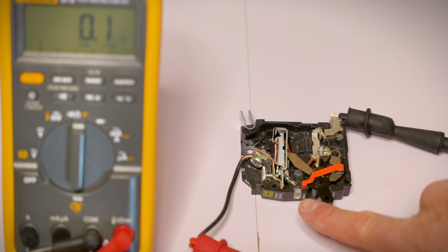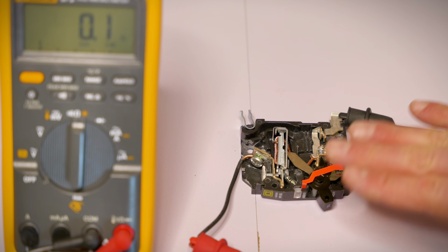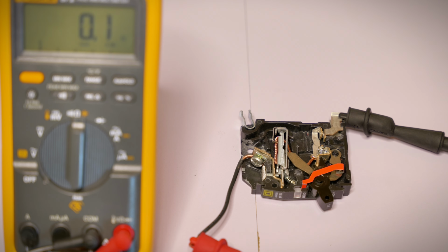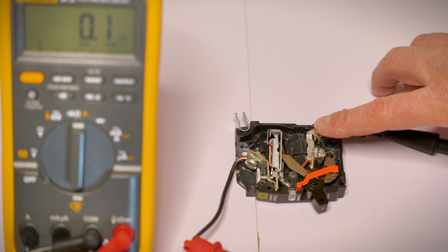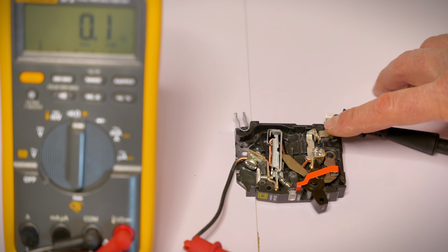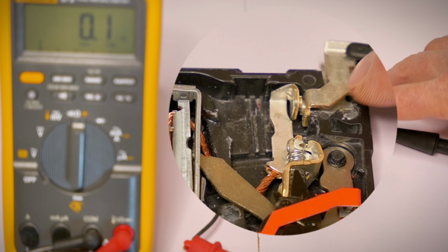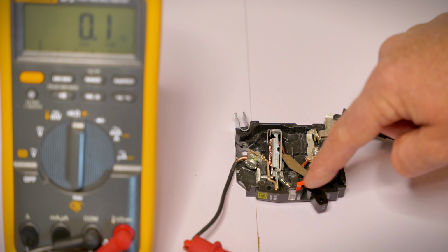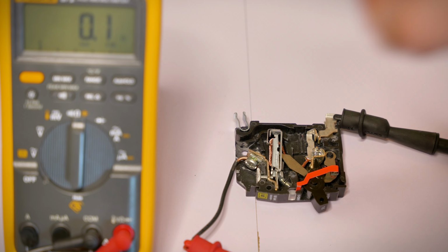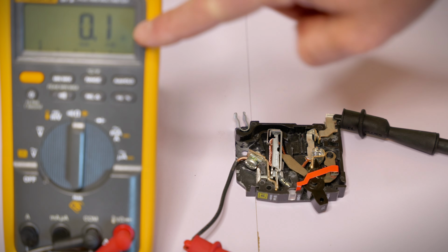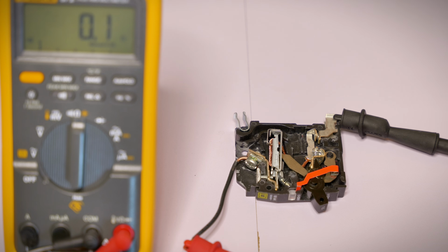You no longer have the orange flag in the window, so everything seems to be operating normal with the circuit breaker. You can also tell that the moving contact arm there is now making connection with the non-moving terminal. So our circuit is being made through the circuit breaker, and you can verify that with the 0.1 ohms or with the continuity tone. So the circuit breaker is working as it normally should right now in the on condition.